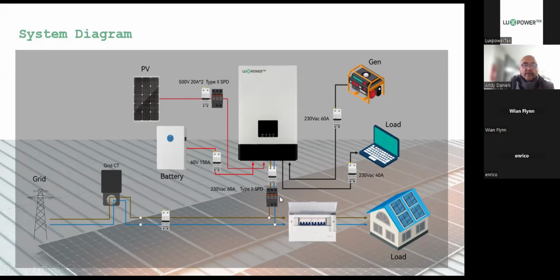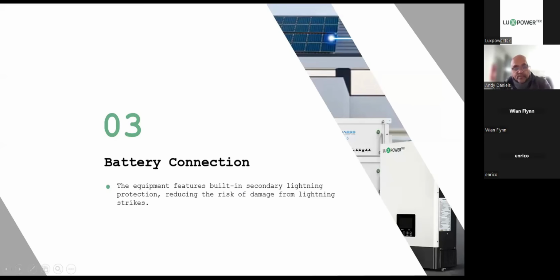And then on this side, we have the DC side. Here we have the PV. Once again, PV comes in through a SPD, a DC SPD, as well as a set of fuses and circuit breaker to the PV input, and then the battery exactly the same through a rated circuit breaker, double pole to the machine. You can use either a circuit breaker or the blade fuses, whichever suits you, but it has to be rated according to the requirements of the machine. Right, so the next step we're going to look at is the battery connection.